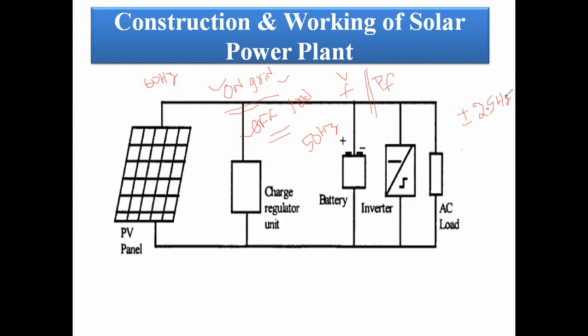The voltage is also per the Indian standard. Theoretically, we study 230 volt plus or minus 12 volt, so the variation is there. For us, we are receiving 218 volt to 242 volt. Theoretically we study 230 volt, but practically we are getting 218 or 220 volt. In the on-grid mechanism without the battery, we can synchronize the parameters and feed directly into the grid. Here one smart meter is connected, and we can measure how much electricity is generated.